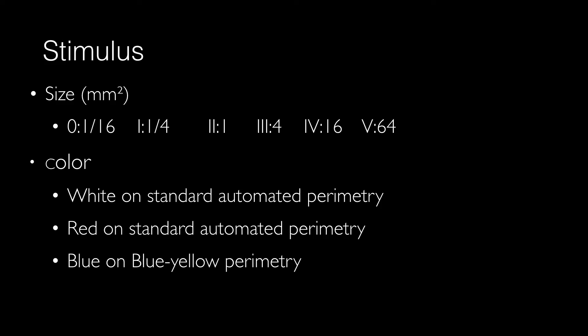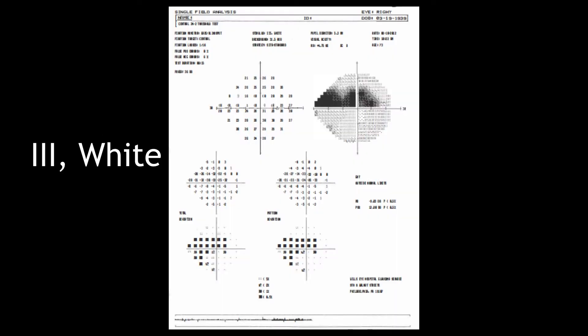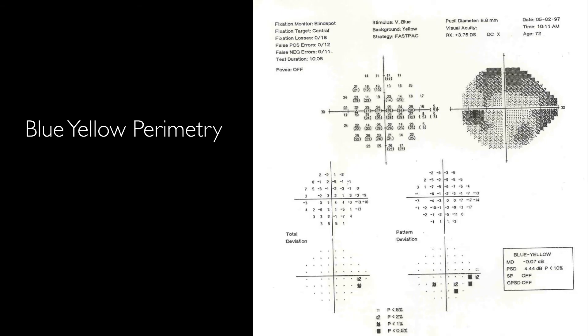We have five different stimuli in the Humphrey visual field and we generally use size three and five. In terms of color we have white, red, and blue. If we choose size three and white, because the machine has a normal database for this stimulus, we will get a three-in-one printout. In blue-yellow perimetry there is a normal database for stimulus size five color blue, therefore we also get a three-in-one printout.